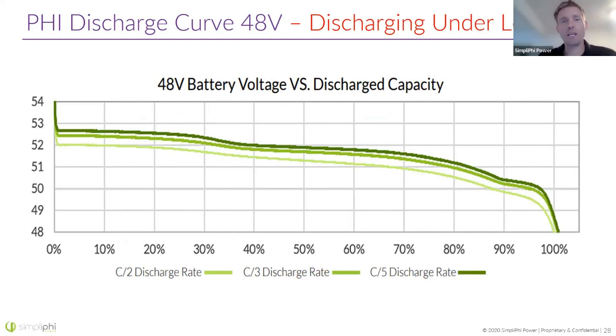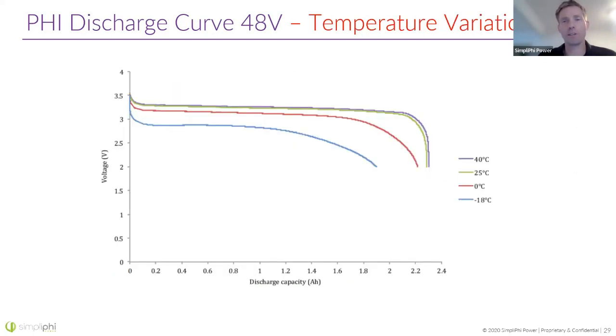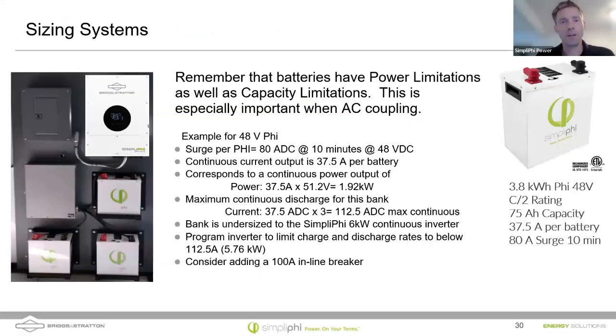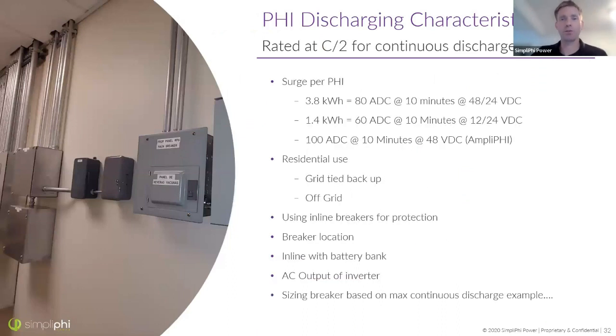At C over 20, you're going to see very little voltage drop across the internal resistance of the battery because the current rate is so small. So it'll almost look like a resting voltage. I'm going to come to that in a second. For the temperature graph, it's the same answer there. Since you're discharging so slowly, you see less of a temperature effect. This is a C over 2 discharge cycle of an LFP battery cell. So I'll come back to that question. It was a good question.